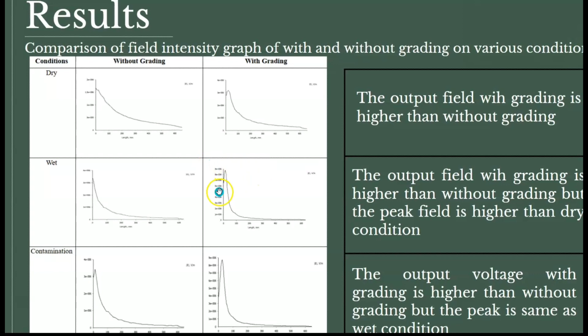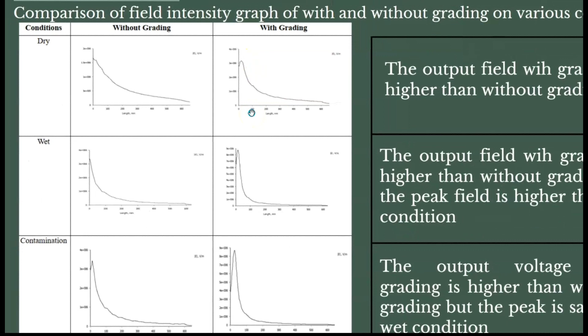For the wet condition, the output field with grading is higher than without grading, and the peak field is higher than in the dry condition. The peak here is about 8 x 10^6 to 9 x 10^6 volts per meter, while for the dry condition it is about 3 to 4 x 10^6 volts per meter.